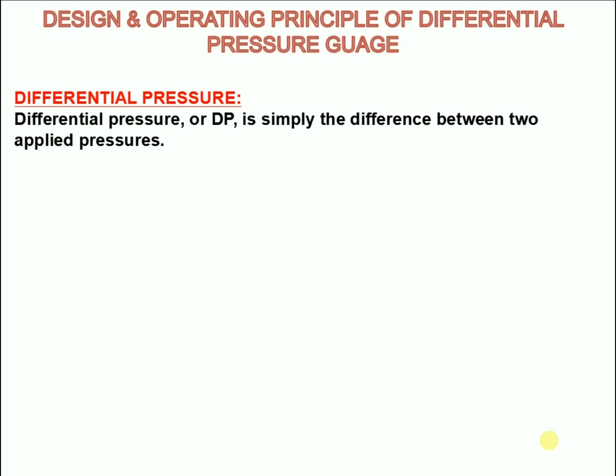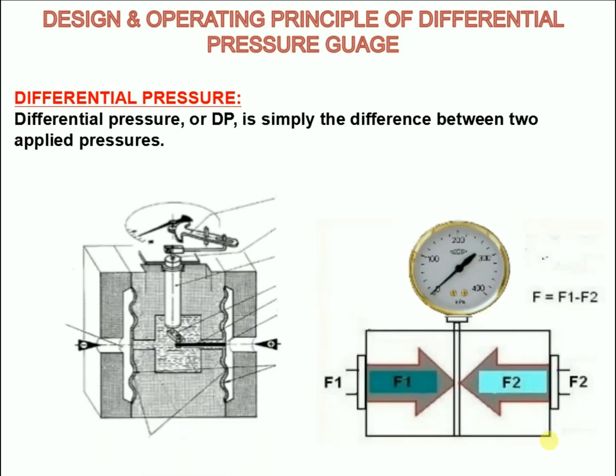A differential pressure gauge is a visual indicator designed to measure the difference between two pressure points within a process system. The gauge usually has two inlet ports that are each connected to the pressure points being monitored.